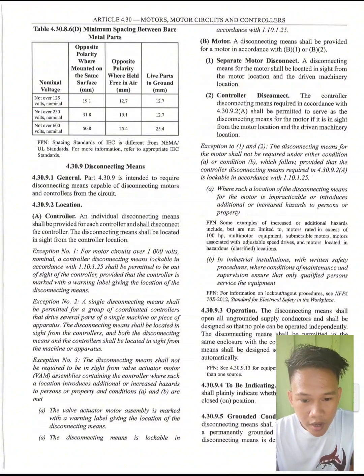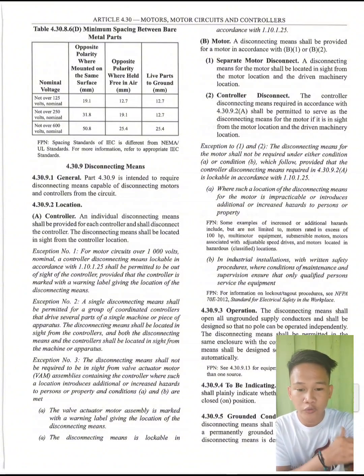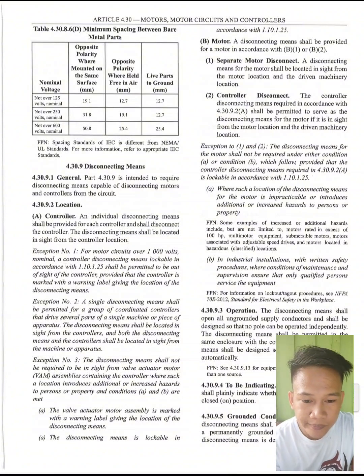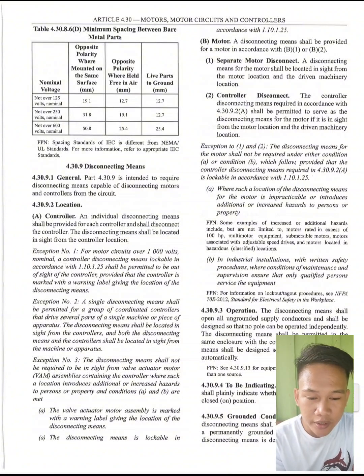So not over 125 volts nominal: opposite polarity where mounted on the same surface, it's 19.1. Then 12.7 for opposite polarity where held free in air. Then 12.7 for live parts to ground. Next, we have not over 250 volts nominal, 31.8 for opposite polarity where mounted on the same surface, 19.1 for opposite polarity where held free in air, and 12.7 for live parts to ground.